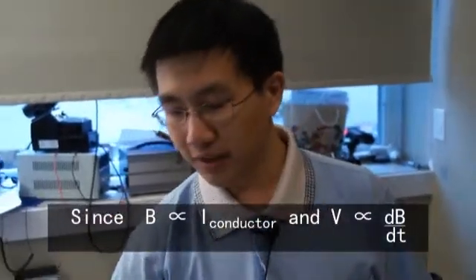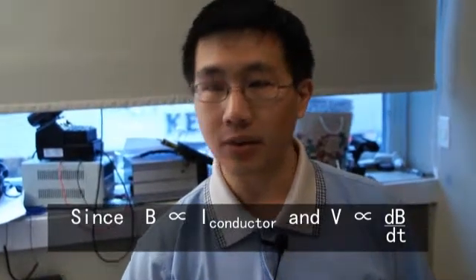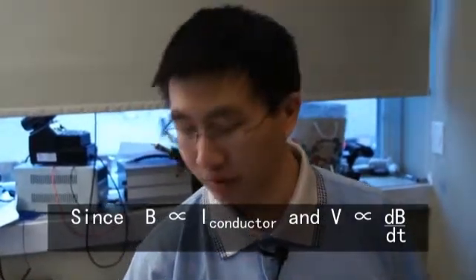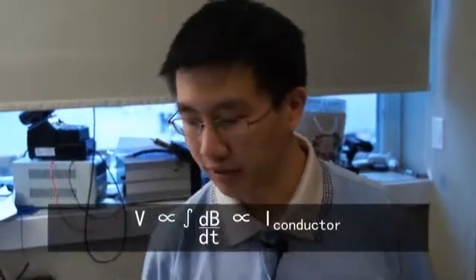So the Rogowski coil produces a voltage proportional to dB/dt, and in order to turn that into a signal that's proportional to the current flowing through the conductor, you need an integrator. Now, inside this enclosure is the integrator.